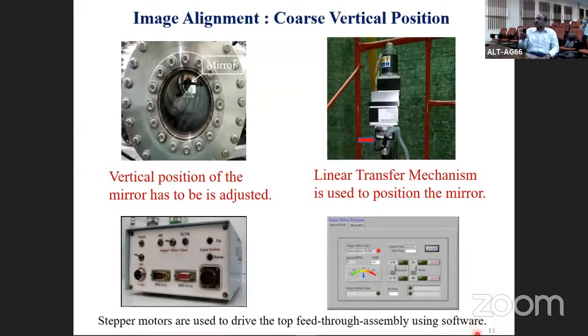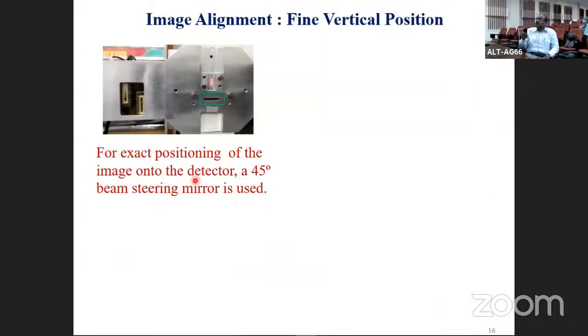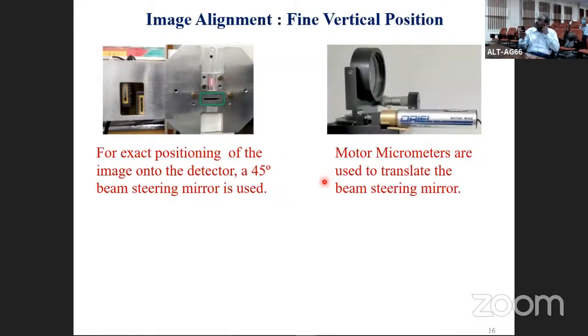The exact position of the image is accomplished through a 45-degree beam steering mirror. So you have a detector here. This is our secondary optical lever, which is used for the control application. We use a 45-degree beam steering mirror driven by motor micrometers to translate the beam to get it onto the detector. So how do we do that? You are not sure where your image is. You have done the manual adjustment on the field of view of a mirror and left it.